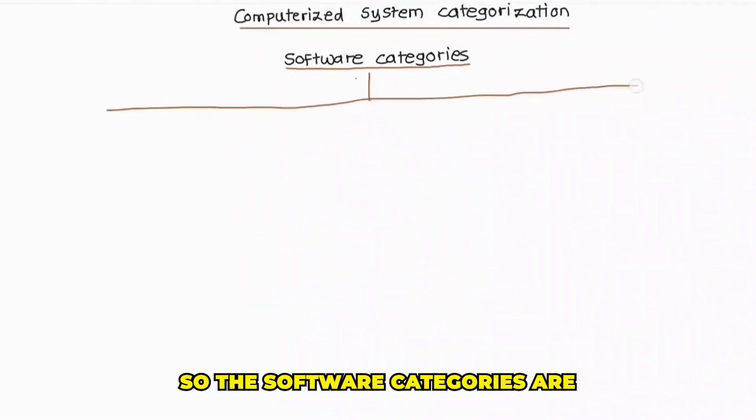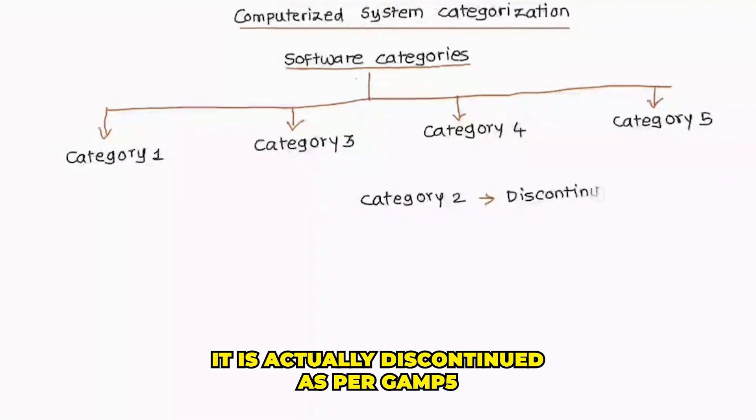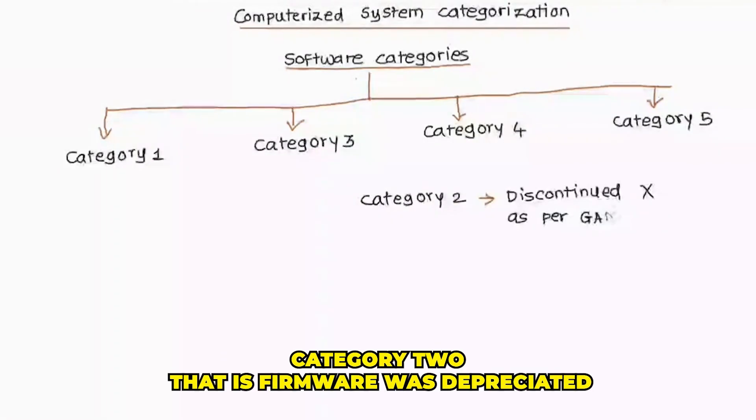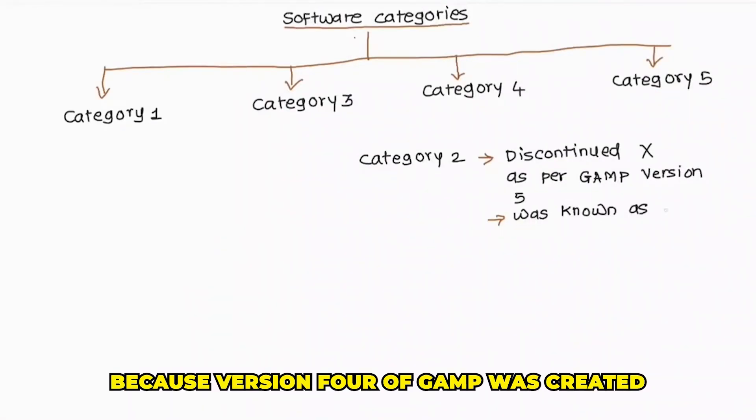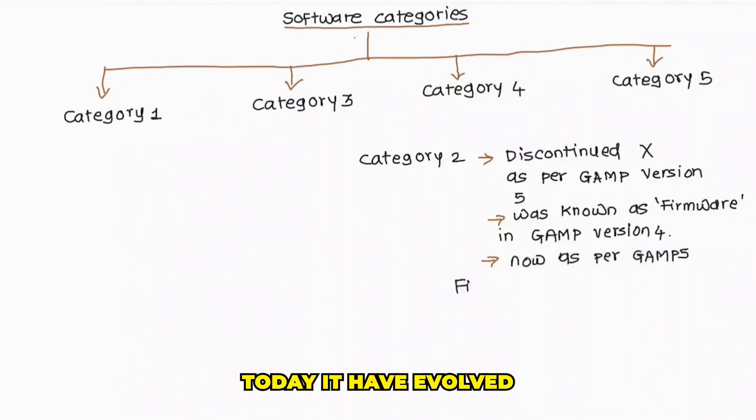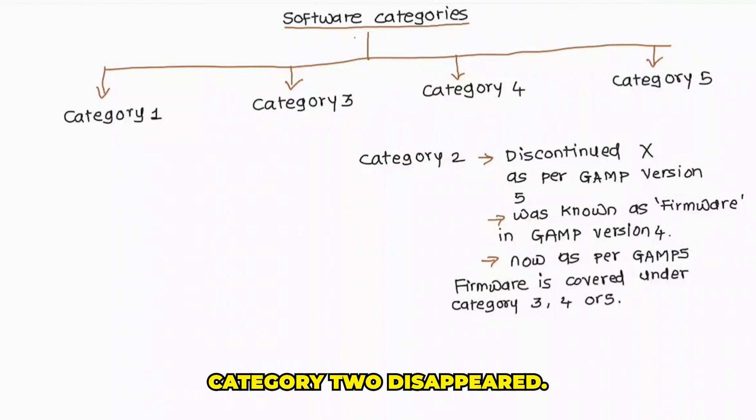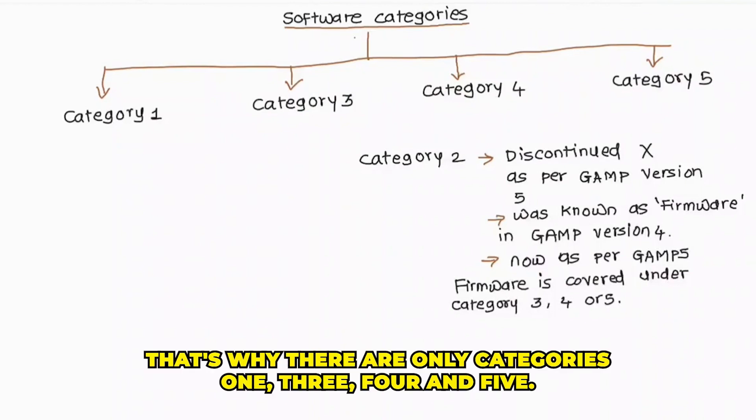The software categories are category 1, category 3, category 4, and category 5. No, I did not miss category 2. It is actually discontinued as per GAMP 5. Category 2, that is firmware, was deprecated because when version 4 of GAMP was created, the firmware differed from rest of the categories with its own characteristics. Today, it has evolved so that most firmware can be classified under category 3, 4, or 5. That's why there are only categories 1, 3, 4, and 5.